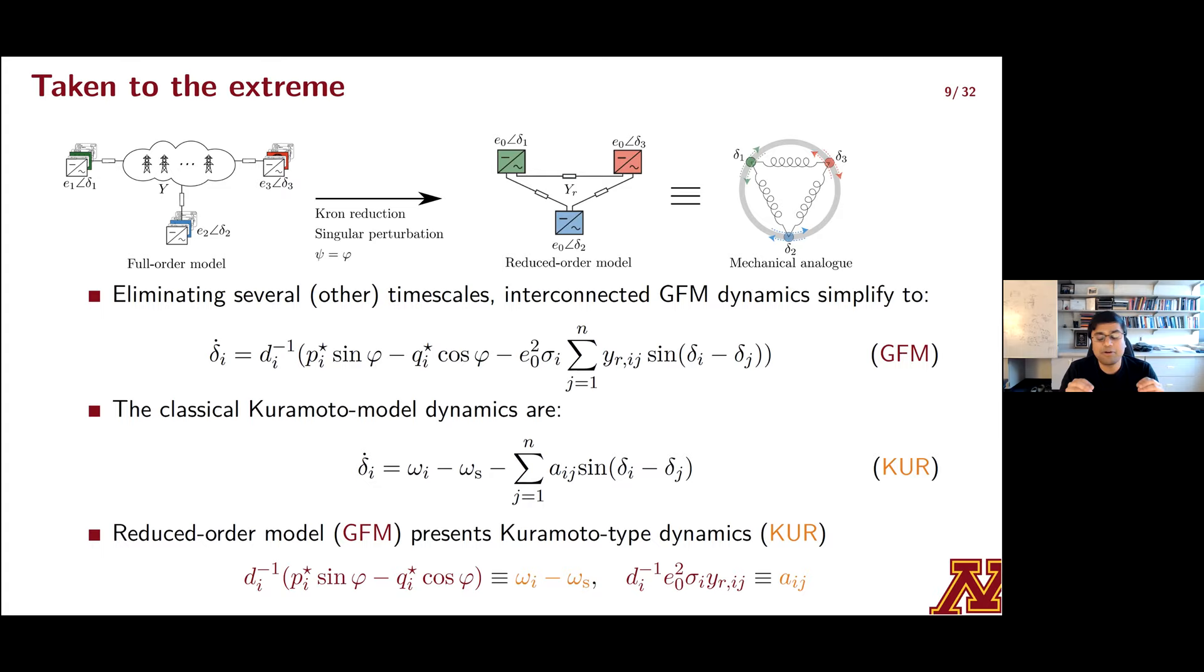And you assume that the GFM resources are all tuned so that their rotation angles that are in their primary controllers exactly match the impedance angles of the interconnecting transmission lines, then what you get is a reduced order model for the phase dynamics shown in this equation tagged GFM. This is all that's left. Entries D sub I are actually encoding the frequency power droop behavior. This is going to be different depending on what type of GFM resource you have.